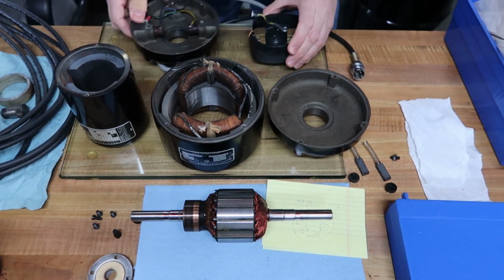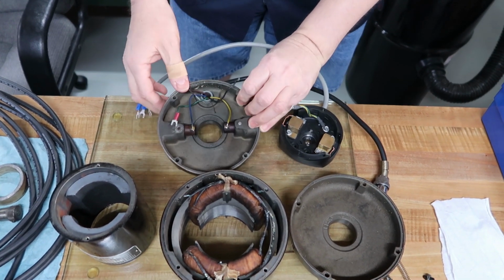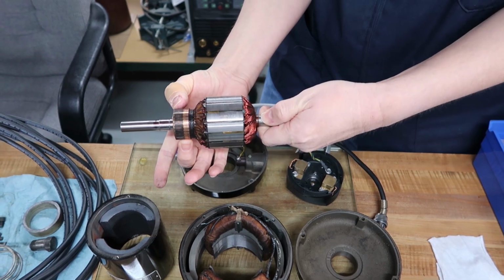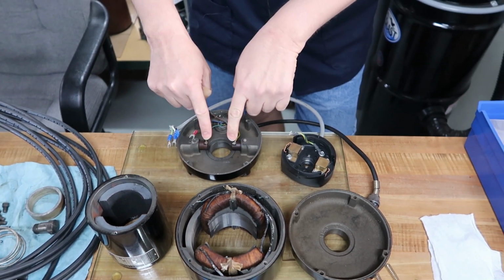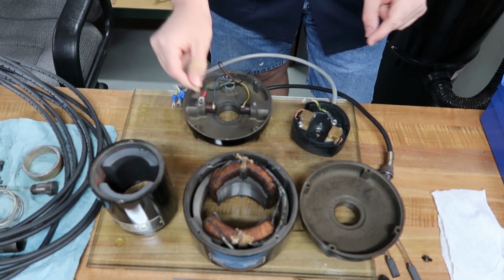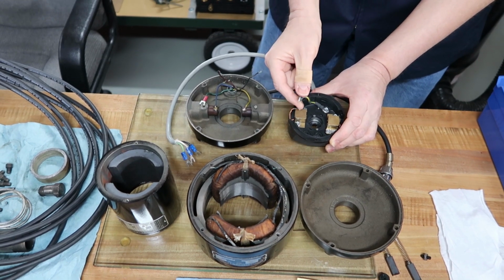If you look at the armature end of the 2 motors, they're really identical. This is the cap on the older motor, and a cord comes through. You can see 2 of the conductors go to the brushes. I'll bring this over to make it easy. The 2 brushes ride on the commutator, which powers the armature windings. So you've got 2 wire conductors for the brushes, 2 conductors which tie into the shunt or field windings, and then the 5th conductor for ground. Whereas the permanent magnet DC motor has just the 2 wires for the brushes and a 3rd wire for the motor ground.